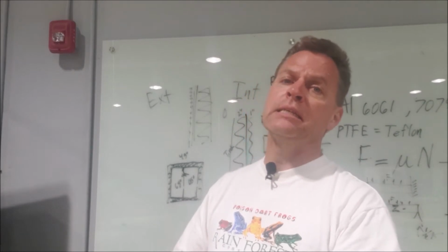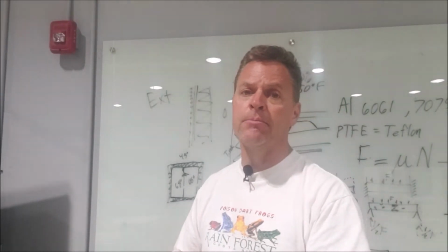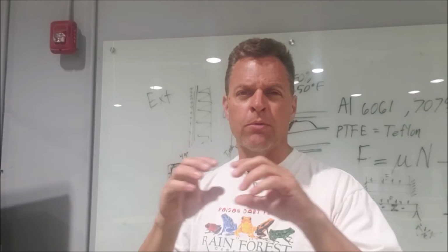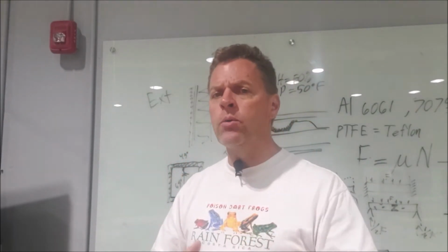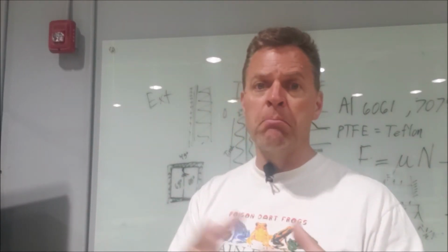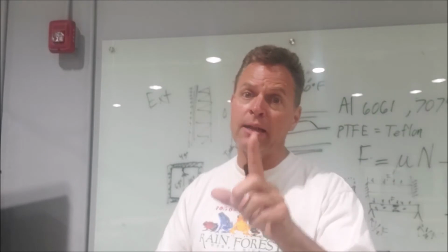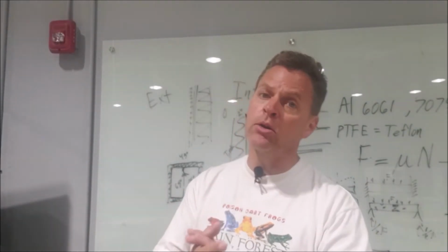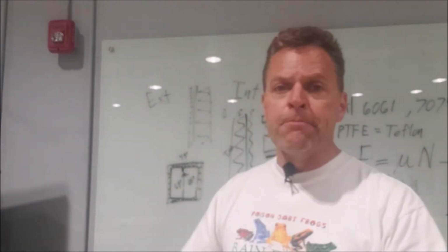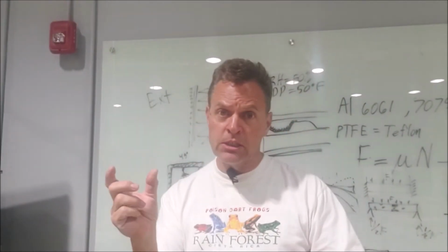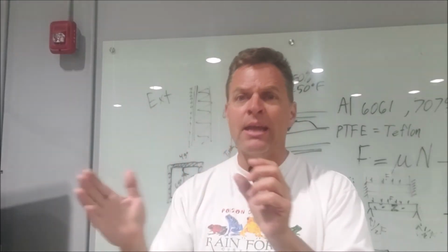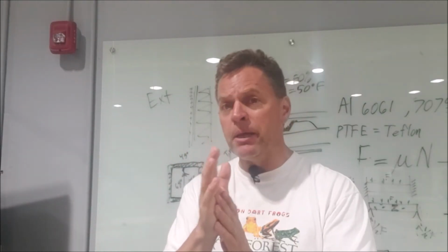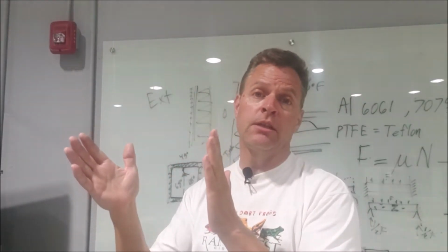So that's one of the reasons I did not select some of those foam boards, or a solid board insulation foam. Instead, going with GPS, it looks like black polystyrene, and it's only about an R value of 5 per inch, but it doesn't degrade with time, and it's better at cold temperature. So that's what I've selected. 1 inch on the interior, 2 inches on the exterior. Again, with that concept of not letting the metal get as cold as it could be. So that's putting the 2 inches of insulation on the outside.